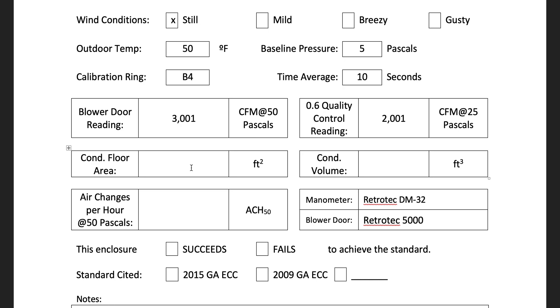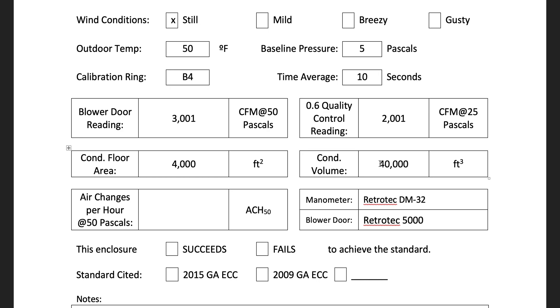Conditioned floor area — obviously very important. Let's call this 4,000 square feet. And the conditioned volume: you want to know exactly what this is. If I'm checking somebody's work and looking at a report sent to me to double-check, I would be looking for the conditioned floor area times roughly 9 or 10 feet, so something in the neighborhood of 40,000 cubic feet. That's basically the square footage times the ceiling height — and if you use 9 feet, you're counting the floor cavities between floors, which truly is probably part of the conditioned volume.